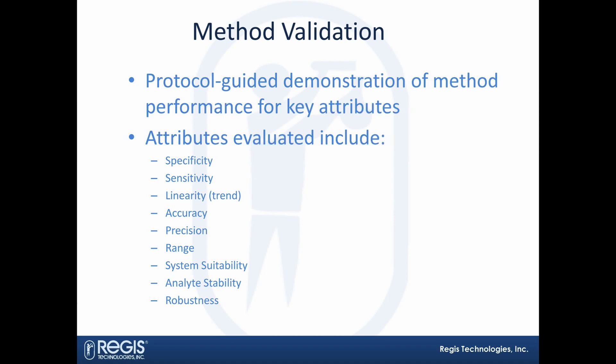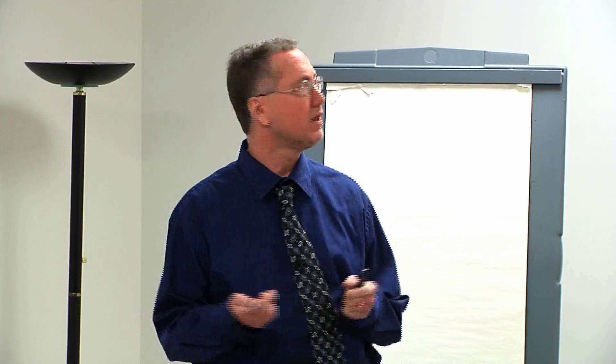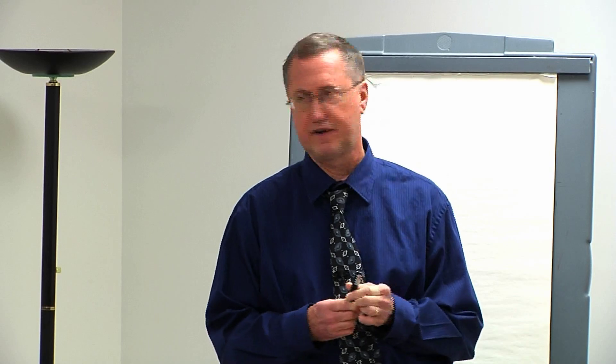Key performance attributes of method validation are: specificity, which means you want to look at the right thing — you may have negative controls such as blanks to show it's discriminatory. Sensitivity is how low you can go in detecting what you need to find. Linearity or trend is the ability to see a relationship between response and concentration. Accuracy is closest to a true value, and can also be seen as recovery from spike samples. Precision is variability.